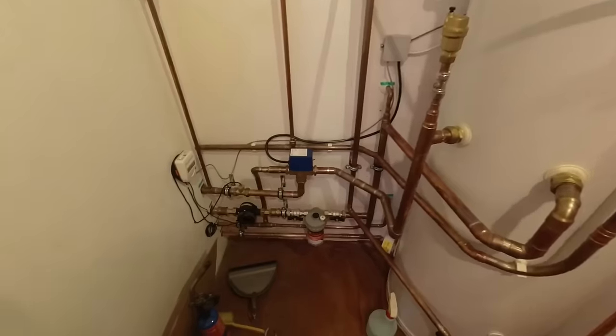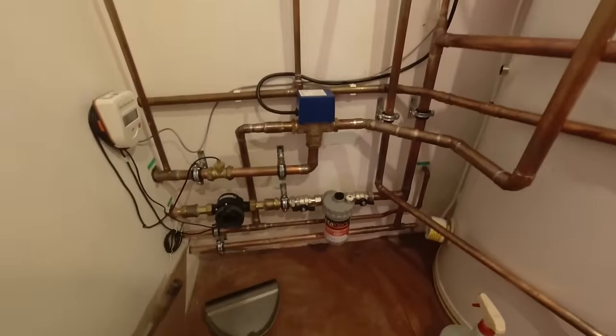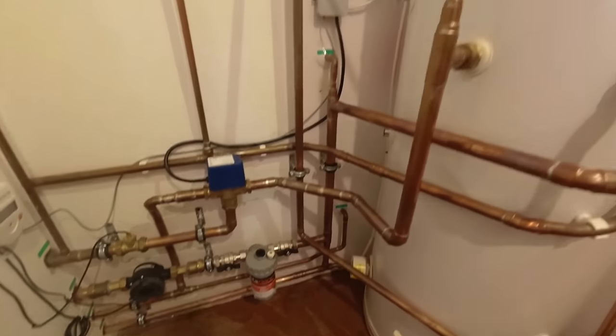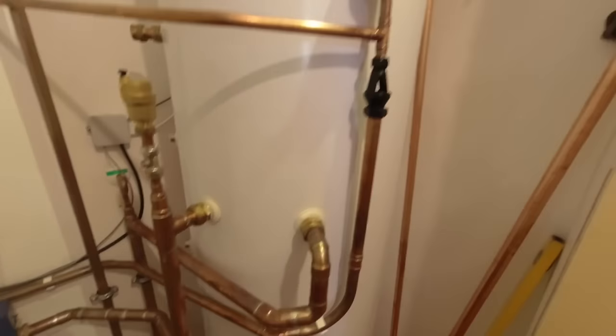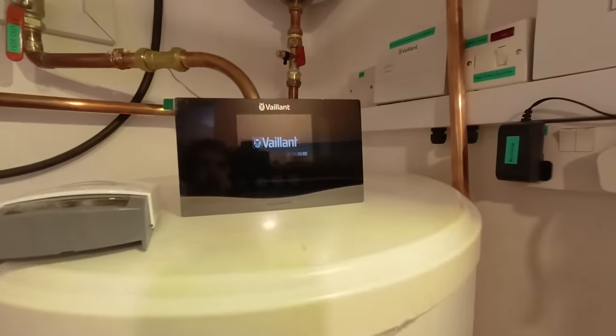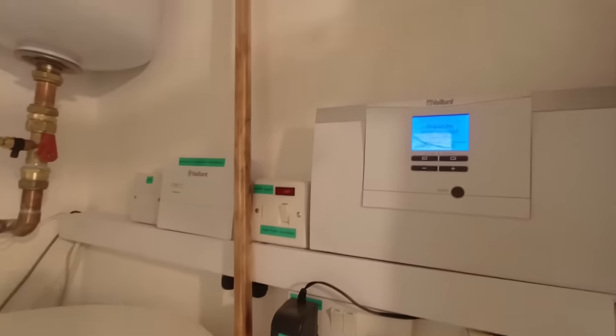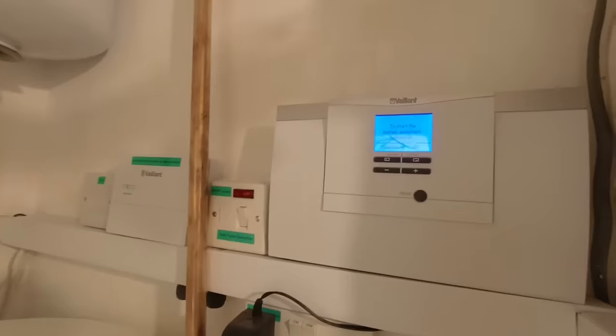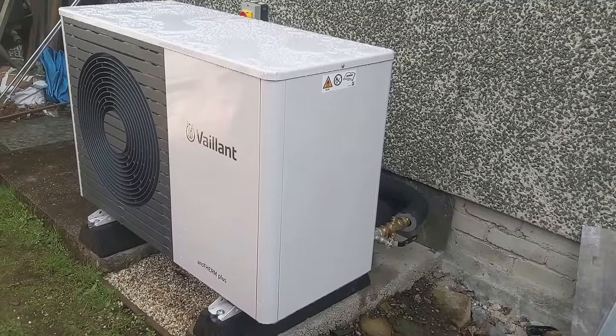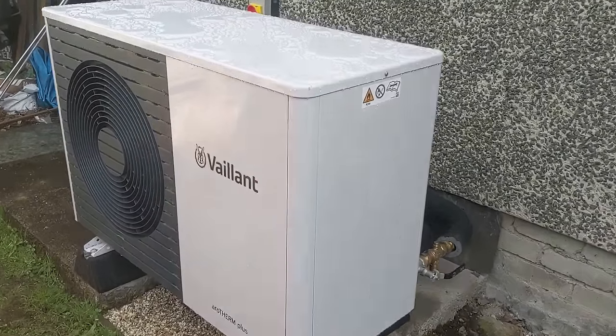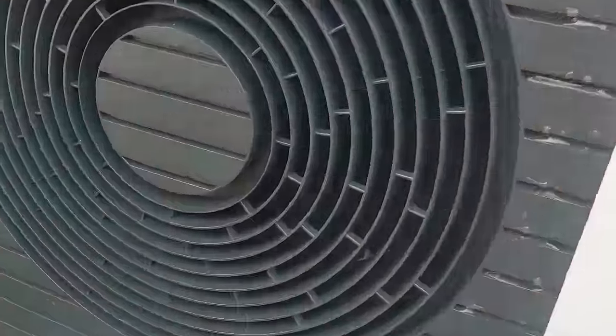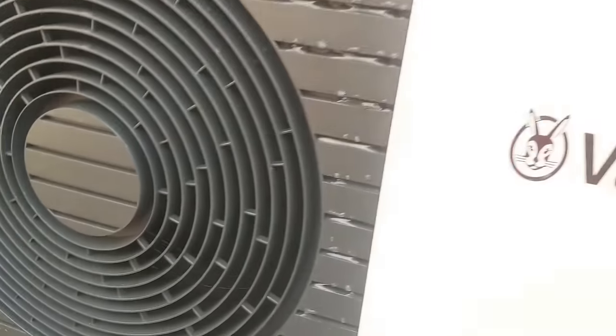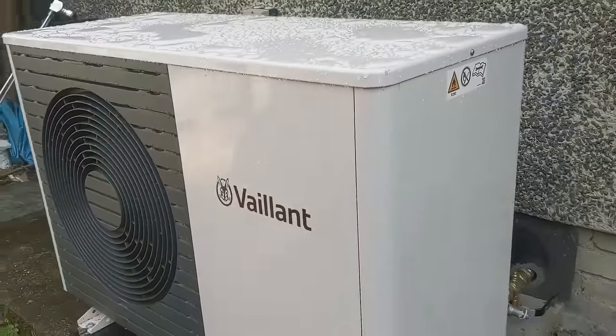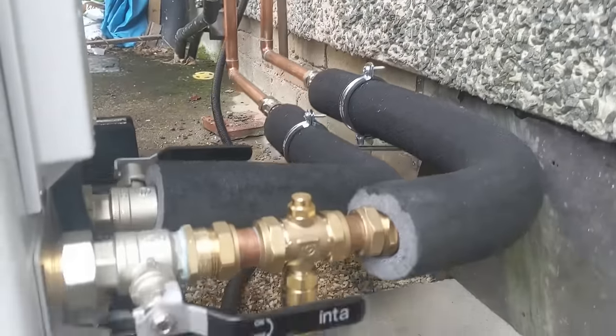and earth. Hey, outdoor unit's just been switched on and the pump's just started up. I can hear water running through all the pipes, which is a good sign. And the controls here are just booting up. So I'm just going to run through the install process. Hey, success! So the heat pump is now up and running. It's currently heating the hot water. And it's so quiet. It's amazing, these Vaillant units. So quiet. And obviously I need to do the installation, but I just thought I'd get it up and running so I can test and check for leaks and everything.